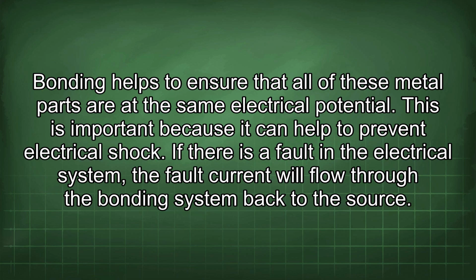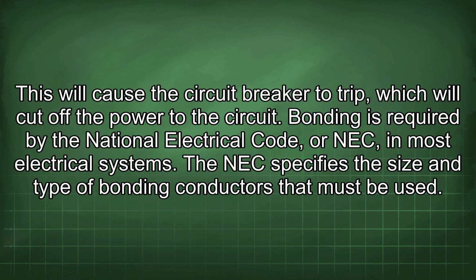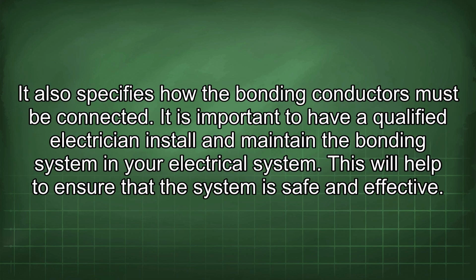If there is a fault in the electrical system, the fault current will flow through the bonding system back to the source. This will cause the circuit breaker to trip, which will cut off the power to the circuit. Bonding is required by the National Electrical Code, or NEC, in most electrical systems. The NEC specifies the size and type of bonding conductors that must be used. It also specifies how the bonding conductors must be connected.